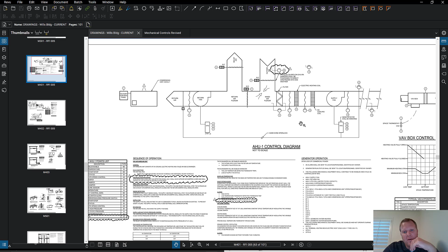What do you need in order to flush piping? Well, you need to run water through it. And how do you run water? You need a pump. So in planning some of this stuff, getting power to pumps sometimes is critical. I might need power to the pump before I ever need power to the boiler, so I can pressure test, then flush, then fill, then condition that piping.